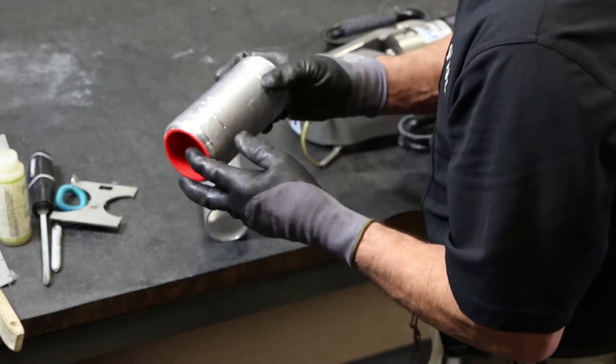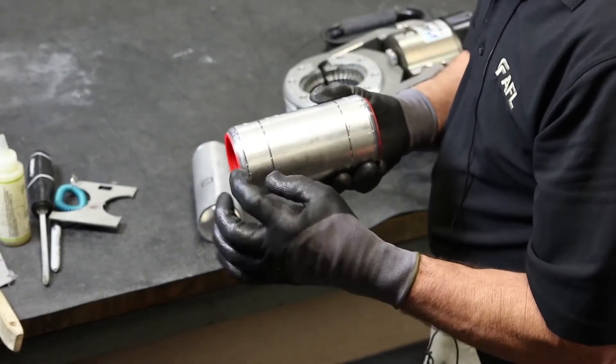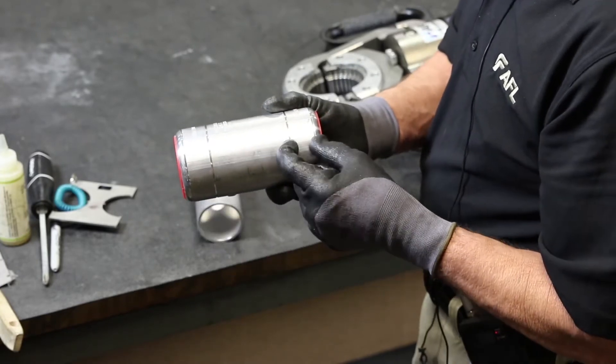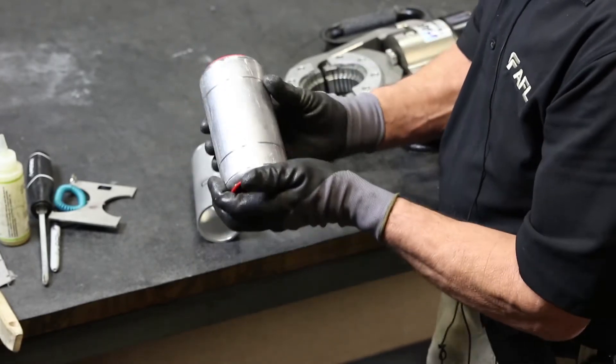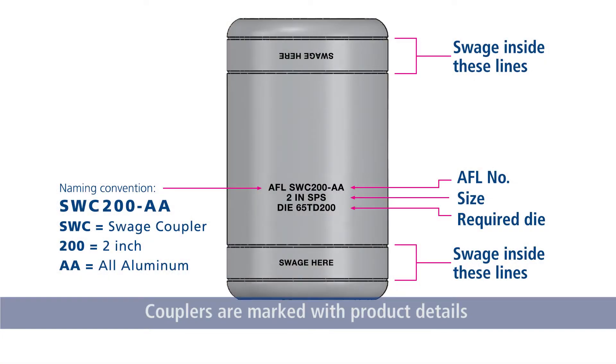Any bus fitting from one inch to four inch only has one compression required per side. In between the two lines, the fitting says 'swage.' It also has the part number, the recommended bus for use with this fitting, as well as the dies to be used with this fitting for proper installation.